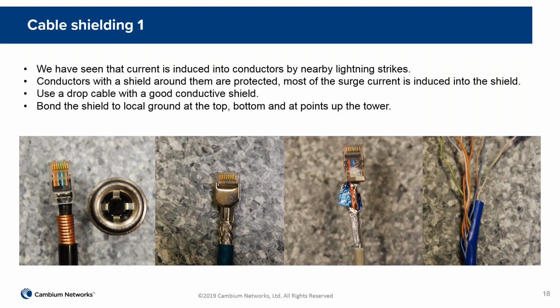So with a shielded cable, we can hopefully put most of the current into the shield and it goes straight to ground. And because the voltages involved are low, because we have low resistances, the amount of power dissipated in our cabling, in our connections, is very low as well. So I've got some pictures here of various forms of cable that we might come across in our installations.